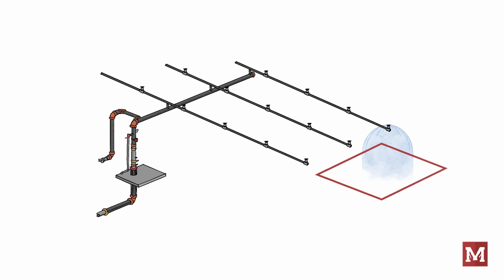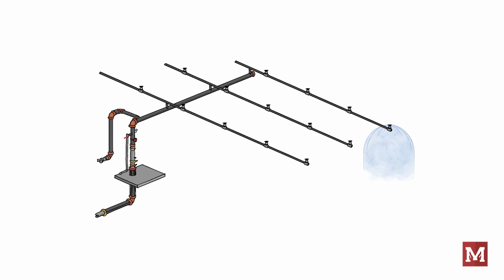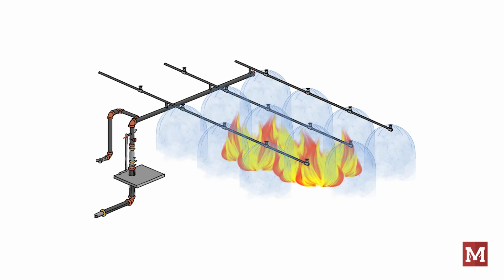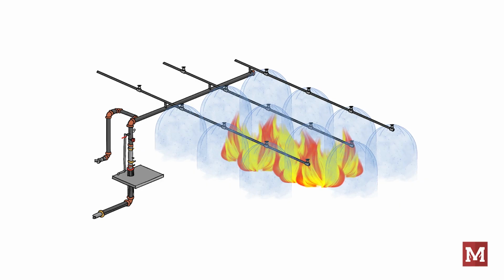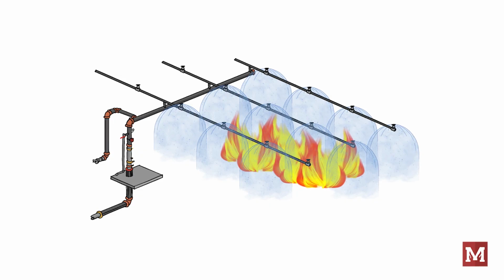So that area, the amount of area that sprinkler is covering, affects how much effective density that sprinkler is going to have. And we know from our basic building blocks of fire protection, higher densities of water will be able to cool the fire faster by absorbing much more heat. So let's talk about two drivers that affect the most demanding sprinkler. Whichever demands more will rule the day. That is, whichever factor needs a higher starting pressure will become the driver for that most demanding sprinkler. Let's talk about the two drivers.